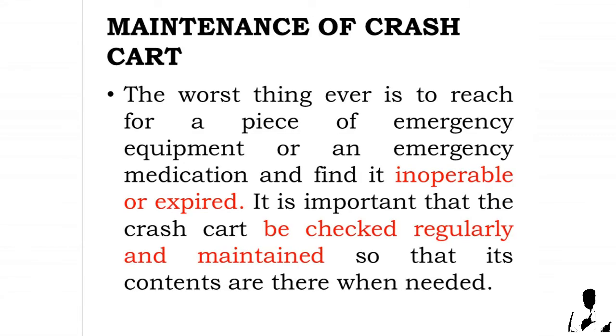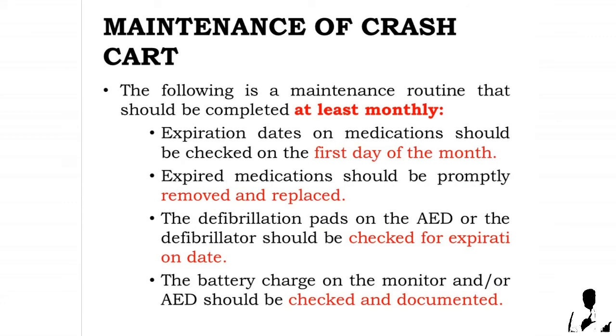Maintenance of crash cart: The worst thing is to reach for emergency equipment or medication and find it inoperable or expired. It is important that the crash cart be checked regularly so its contents are there when needed. The following maintenance routine should be completed at least monthly: expiration dates on medications should be checked on the first day of the month and expired medications promptly removed and replaced. The defibrillation pads and AED should be checked for expiration, and the battery charge on the monitor or AED should be checked and documented.